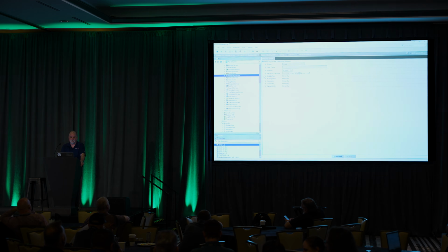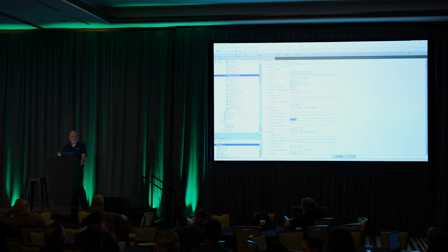So going back to this hierarchy, you can see that we can use elements here to search for things that have a certain tag. Like, I want to find everything that's been identified as a floor in the building or space or something like that. And then I want to know the children of that component that happen to be some kind of equipment, in this case, an air handler. And then we can show points and things like that as well. But what I want to emphasize is that you don't have to have applied a Haystack data model to do this.